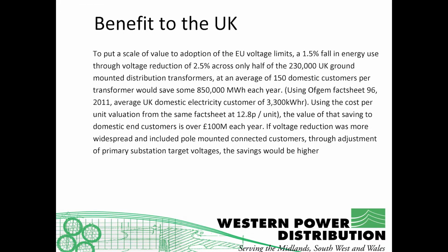To put a scale of value on the adoption of the EU limits, a 1.5% fall in energy use through a voltage reduction of 2.5% across only half of the UK's ground-mounted distribution transformers, with an average of 150 customers per transformer, would save approximately 850,000 megawatt hours a year. And using Ofgem's fact sheet, an average UK domestic electric customer using 3,300 kilowatt hours a year at 12.8 pence a unit, this could save domestic customers over £100 million each year. And if the voltage reduction was more widespread, so if we did it at primary level, then you could save even more.